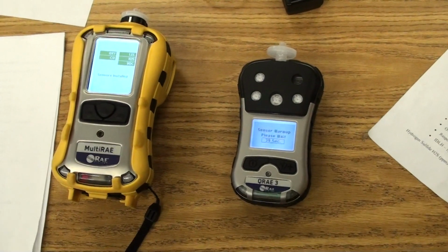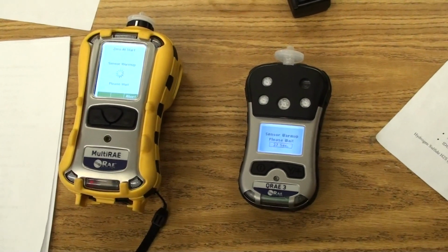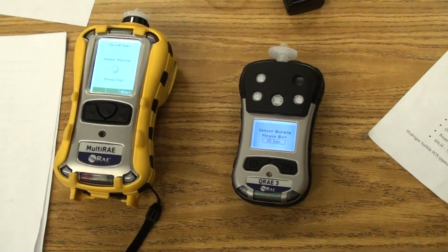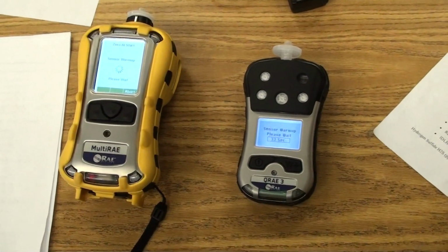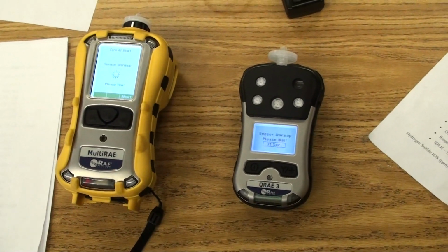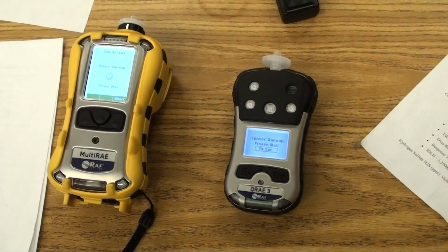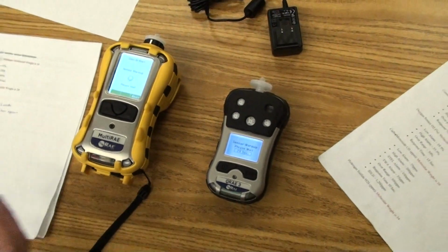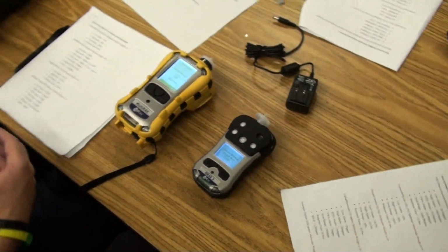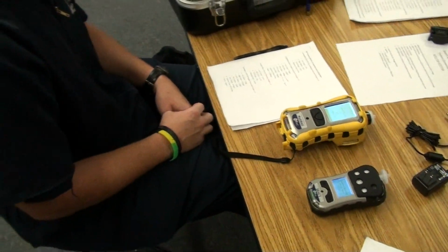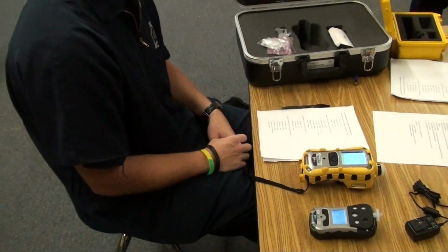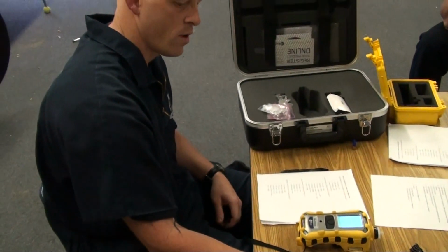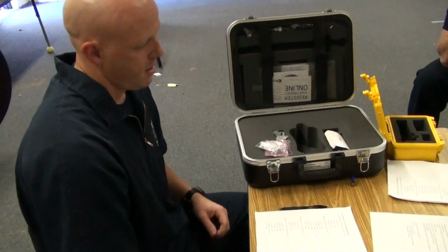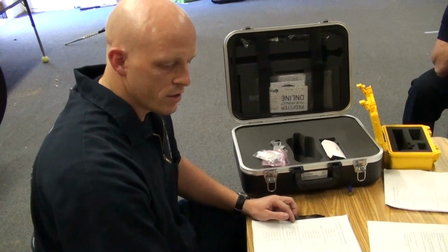You have two options. You can either hit select and start a fresh air calibration, or hit abort, and it just goes straight to the main menu. Every morning when we're doing this, we want to turn it on. After it warms up, do the fresh air calibration, and then there's something else we'll talk about in a second. So while that's warming up, I'm going to talk about what each one does.